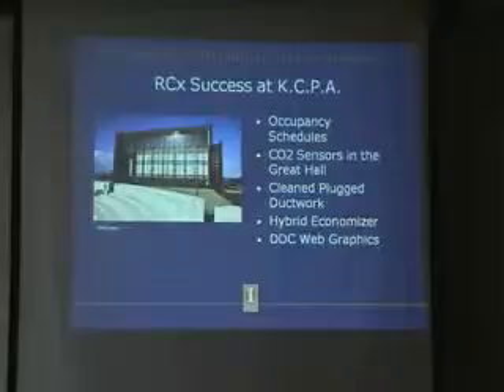We were able to add CO2 sensors in the Great Hall. During the day when that venue was empty, we measured the CO2 level, because that corresponds to people breathing in the space, so it correlates to the number of people. If the CO2 level is low, then we won't open the outdoor air dampers to bring fresh air in.